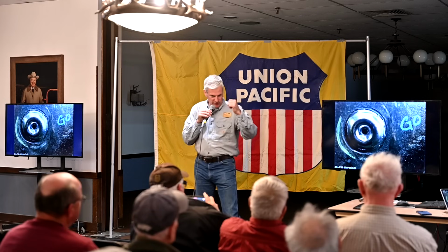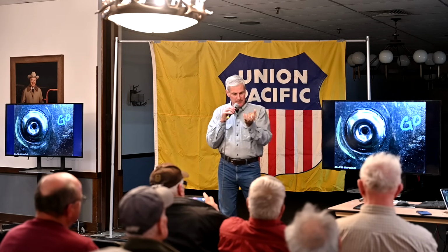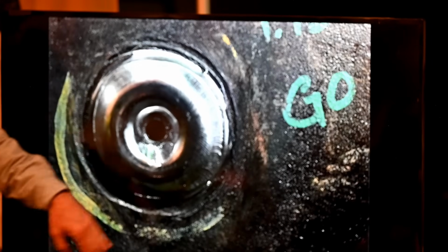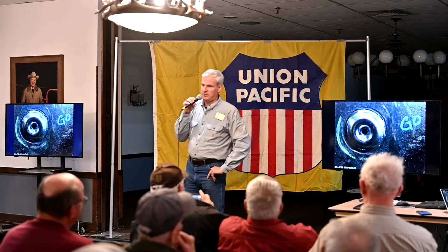I put the forming tool in there, and I pulled a caulking tool out, and it looks like a duck bill. This is a hard part, because you've got to take that little duck bill and shape the metal, bend it into this metal, and just form it. Because if you don't do it, it's going to leak. And then when we've done all this work, months and months of work, we're going to test it.